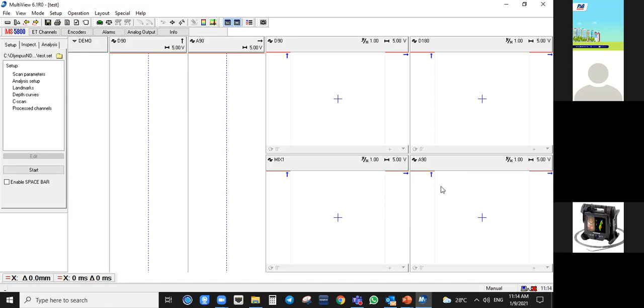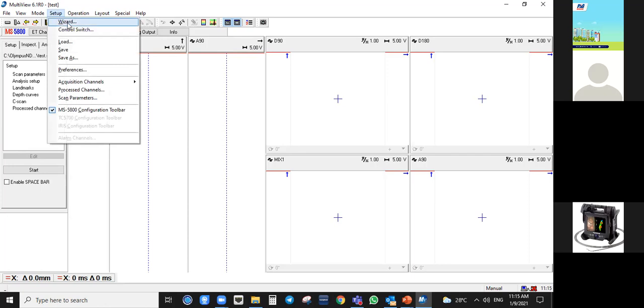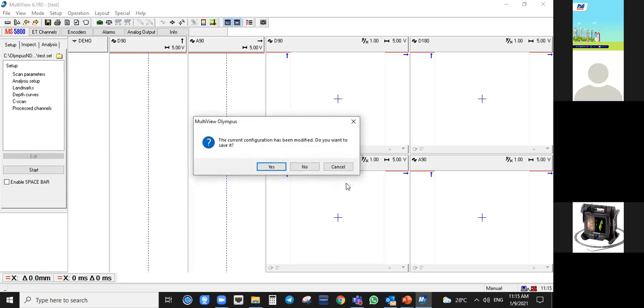Then of course for absolute 90, this channel is used when you are analyzing big defects, like corrosion or erosion. So the first thing that you need to do when you want to do an inspection is to do a setup of your calibration, using the calibration tube that you have. What you do first is under setup, you'll see here wizard. You click on that, and then if you have a previous configuration, you will see this pop-up window. If you don't want to save the previous configuration, just press no. If you want, you just press yes.